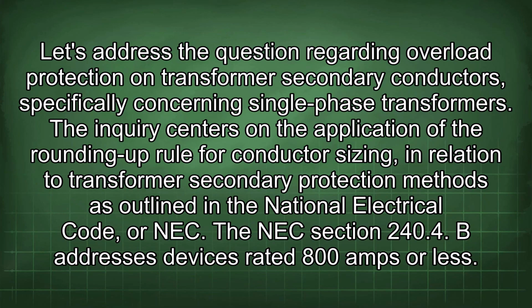Let's address the question regarding overload protection on transformer secondary conductors, specifically concerning single-phase transformers. The inquiry centers on the application of the rounding up rule for conductor sizing in relation to transformer secondary protection methods as outlined in the National Electrical Code, or NEC.